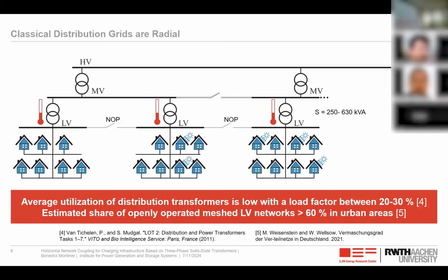But also, and especially in urban areas, we have a grid structure where we have those normally open points in between the different neighboring transformers. And this is there to achieve a faster resupply during a fault or when you have maintenance on one of the transformers. And we need to keep this structure in mind, because I will come back to that later.